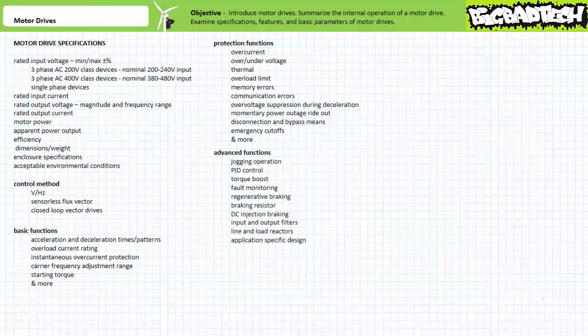Motor drives may also include handy bonus features or options, like jogging operation, PID control, torque boost functions, fault monitoring, whether or not the drive includes a regenerative braking unit or braking resistor, whether or not the drive is capable of DC injection braking, and whether or not the drive includes accessory input and output filters to reduce noise, or line and load reactors to suppress harmonics. Motor drives may also support optimized design features for specific applications, including constant torque applications, variable torque applications, shock or impact loads, constant speed applications, or super high-speed applications.